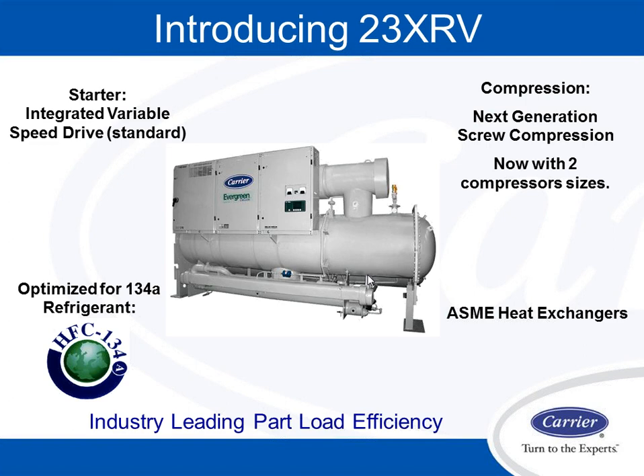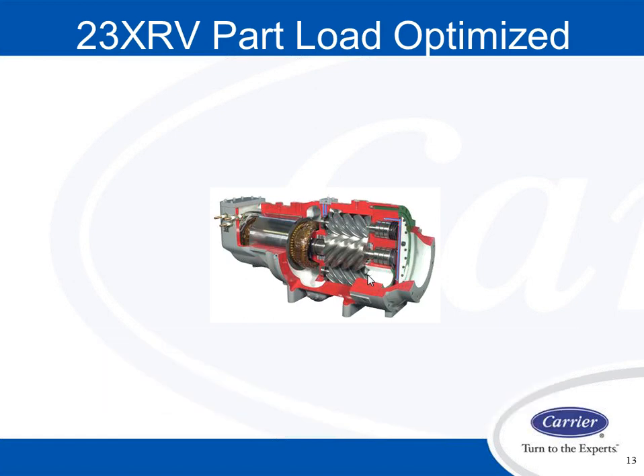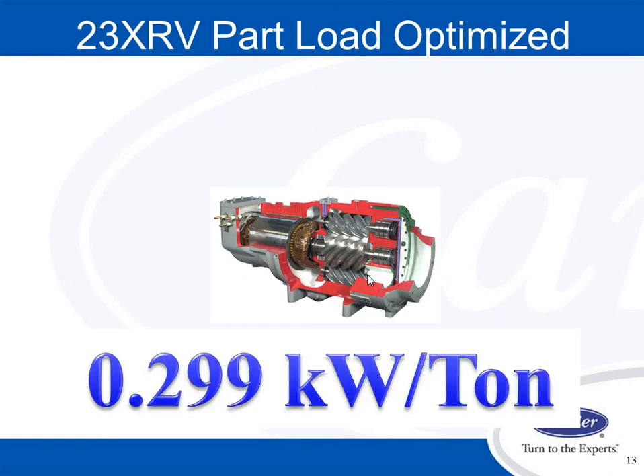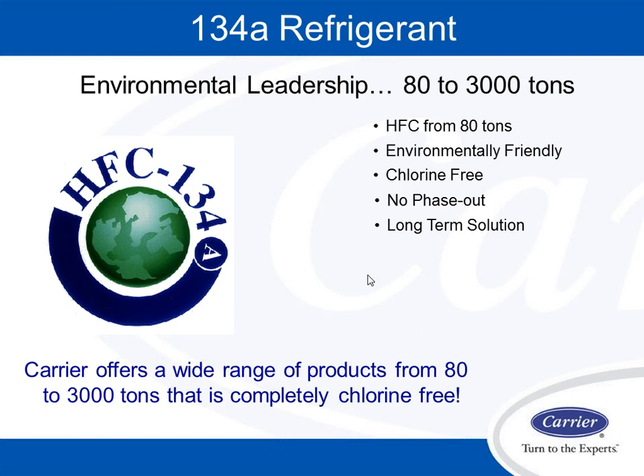Okay, so when they introduced the 23XRV, what we do is we have a standard VFD, standard on the machine. We optimized around 134A. We're using the same ASME pressure vessels that we have for the 19XR and XRV. And now we have the next generation screw compressor, and also the two sizes, so it completely fills the lineup from 250 to 550 tons with industry-leading part load efficiency. I mentioned before that we basically broke the 0.299 kW part load value with our new part load optimized compressor, and we'll go through that in a bit.